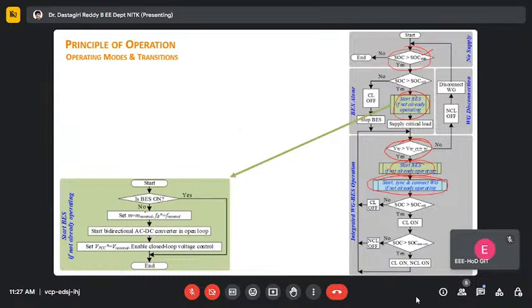First we need to adjust the battery voltage, battery frequency, and battery theta to match the incoming wind, and that's what we are doing here. Once it is done, you synchronize. Then based on the synchronization, based on the power coming from the wind, and based on the state of charge availability, we'll take a decision whether the critical load should be off or on, or the non-critical load should be off or on. So accordingly we'll take decisions based on power balance, just based on power balance.